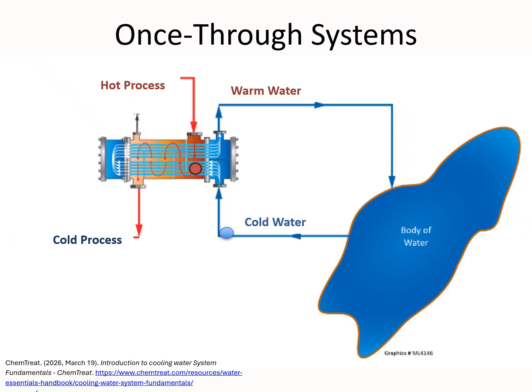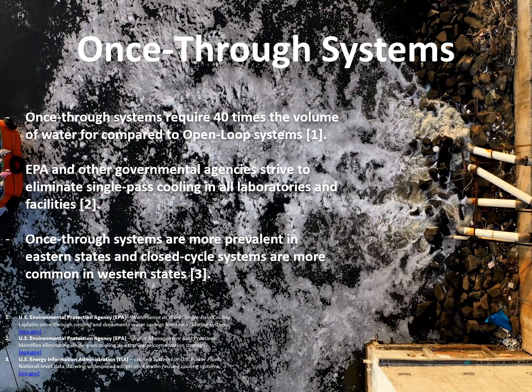Now we will look at various cooling water options that are often utilized by industry and explore their strengths and weaknesses. One option is once-through cooling. This system is the simplest design. It works by withdrawing huge volumes of water from a river, lake, or aquifer, running it through equipment one time, and then discharging it back to the source at a higher temperature. According to sustainability analysis, once-through systems require very high water withdrawals, even though most of it is eventually returned to its origin. There are a few problems, however.